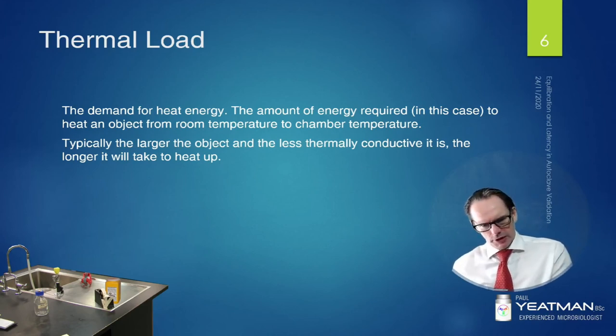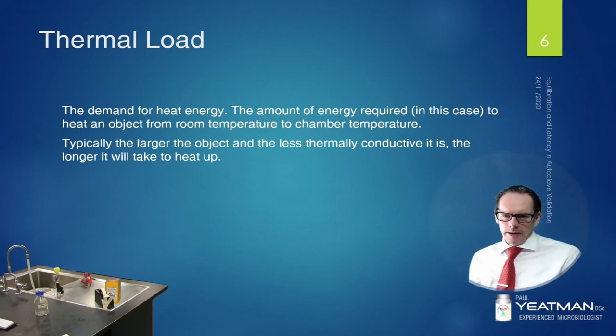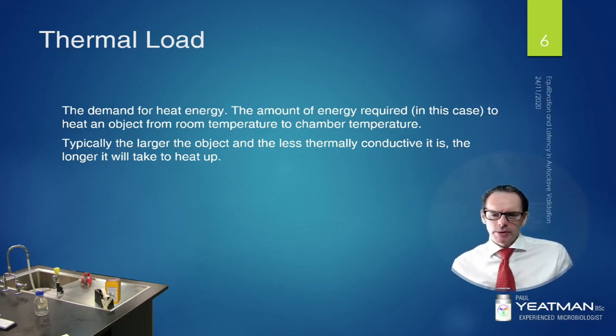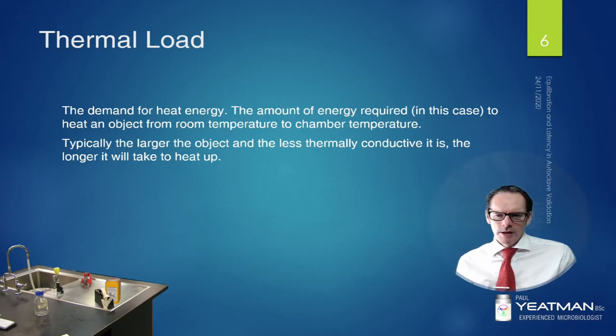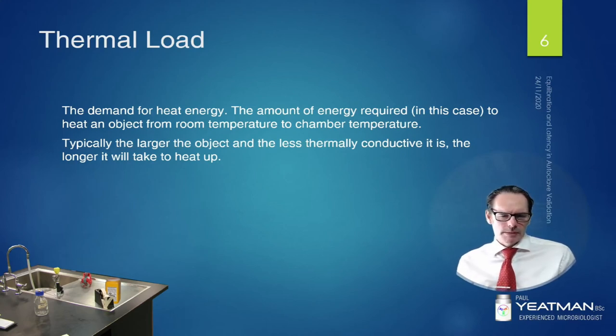So the liquid within the container would actually have to heat up and become steam and therefore moist before it could transfer the heat load, so you might find lag time is different there. With the jam, pickled onions, and milk example from the previous slide, the thermal load of these items is what prevents them from instantly heating up when you move them from the fridge, and it helps keep them cool during periodic door openings.